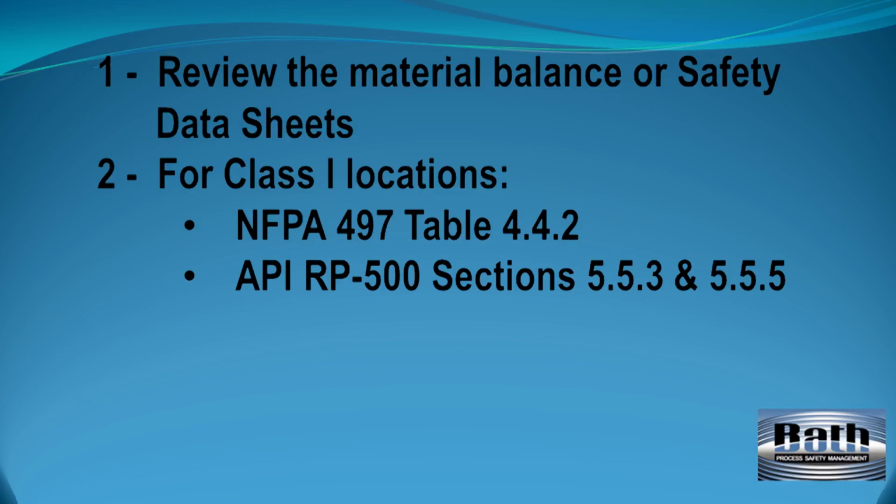Next, refer to API RP 500, 3rd edition, titled Recommended Practices for Classification of Locations for Electrical Installation at Petroleum Facilities classified as Class 1 Division 1 and Division 2. Section 5.5.3 through Section 5.5.5, specific guidelines in these sections refer to locations with rechargeable batteries, mixtures of hydrogen sulfide and natural gas, and assigning Group B to gas streams with hydrogen in concentrations greater than 30% by volume.